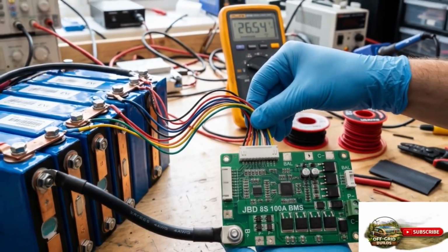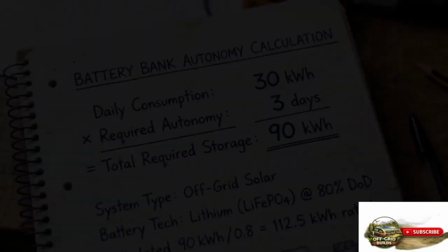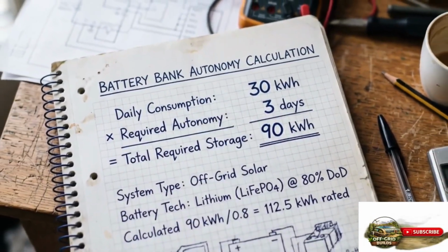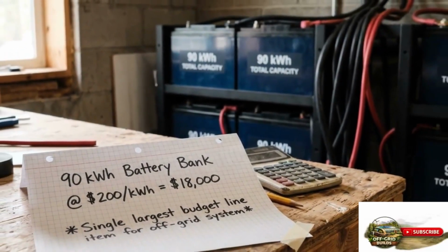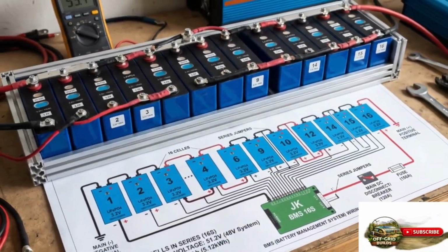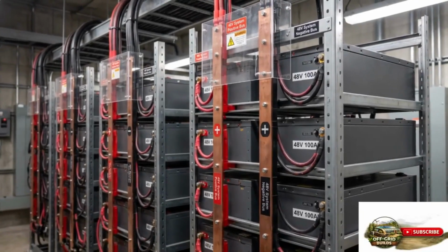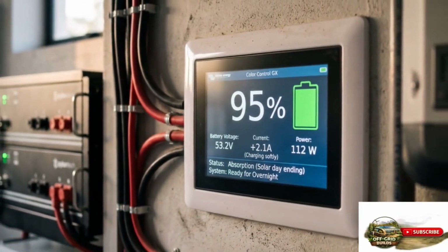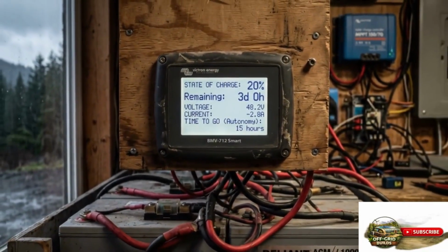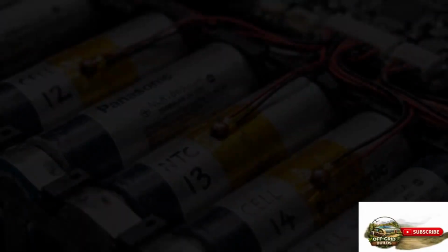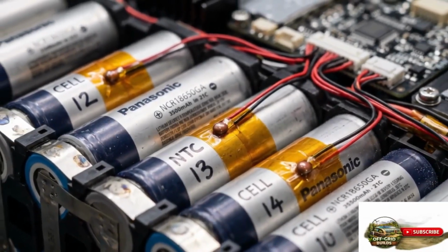A quality lithium iron phosphate battery in 2026 is rated for 3,000 to 6,000 charge-discharge cycles at 80% depth of discharge before capacity degrades to 80% of original. At 1 cycle per day, that is 8 to 16 years of operational life, significantly longer than the 500 to 1,000 cycles typical of flooded lead-acid batteries. Lithium iron phosphate batteries in 2026 cost approximately $150 to $250 per kilowatt-hour of usable capacity when purchased as individual cells from reputable suppliers, or $250 to $400 per kilowatt-hour in packaged battery modules with integrated battery management systems from established manufacturers.